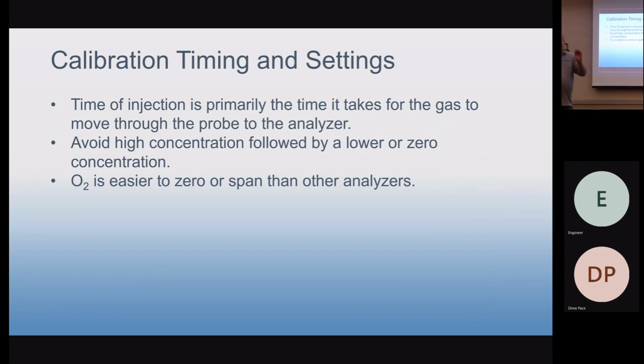Usually, if you watch your O2 analyzer, it'll move from one point to another in just a minute and a half, 2 minutes. It's good, it's stable, it's done, and you can get a good read on it. So we'd follow up after we'd injected all these gases with the O2 span. It did the thing you're talking about, Dave. It's cleared the sample line out, or sorry, the calibration line out of the calibration gas. So it's instrument air or ambient air in there now, and cleared the sample system back to basically ambient conditions.